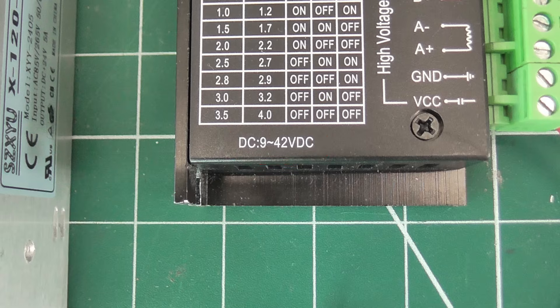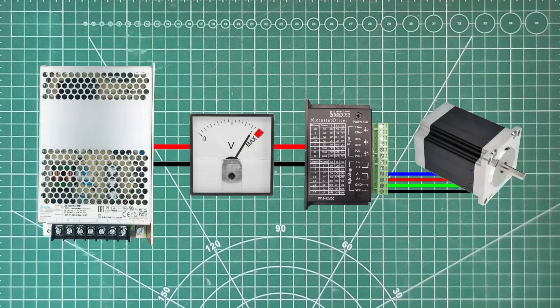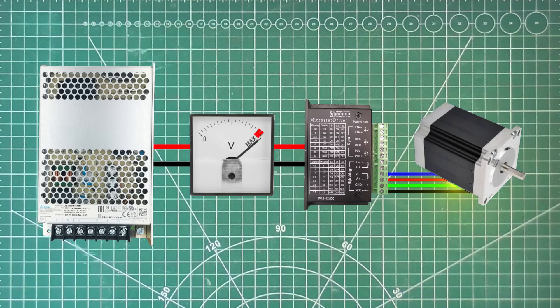But it's important not to go too close to the maximum. A small safety margin is needed, since in some situations, such as decelerating a large load, the motor can act as a generator, pushing power back to the driver and raising the supply voltage. Exceeding the maximum voltage could cause the driver to shut down.